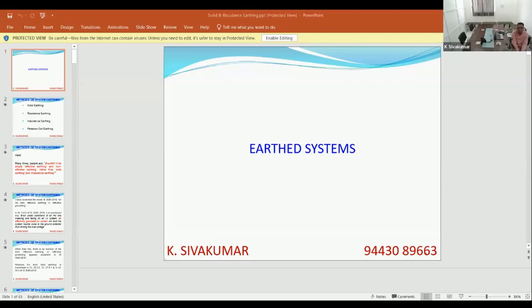Then, from Mr. Abhishek Sarkara, it is shown that for one system of rotating machines you can go for a resistance earthed system, and for the other system you can go for a solidly earthed system. So his question is, it is shown for LV rotating machines to have two connections, one with resistance grounding for rotating machines and the other without. Does it mean, let's say, for an apartment DG requirement to have two numbers, one for lighting load and the other for rotating load or high heating load?